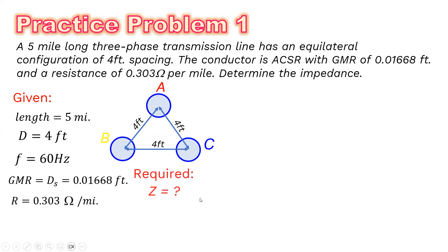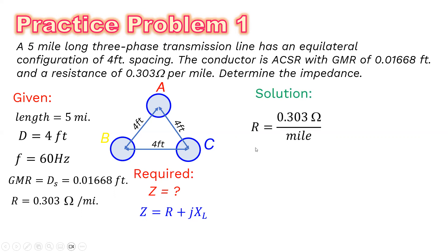We are asked to solve for the impedance, which equals R + jX_L (resistance plus inductive reactance). Solving for resistance first: since the given value is 0.303 ohms per mile, we multiply by the length of 5 miles, giving a resistance of 1.52 ohms.